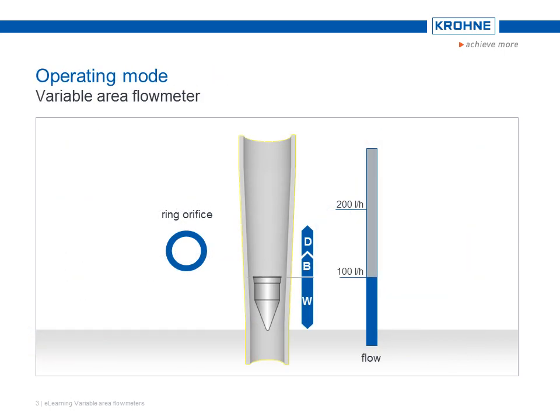To illustrate this with an example: let's take as our starting point a state of equilibrium of the forces — that is, the float remains immobile in a certain position with constant flow. If the flow increases, the flow velocity in the ring orifice also increases, and correspondingly the flow force as well. The float rises.